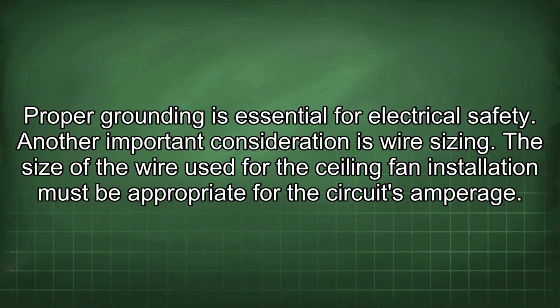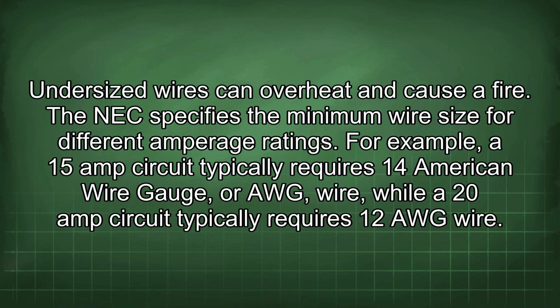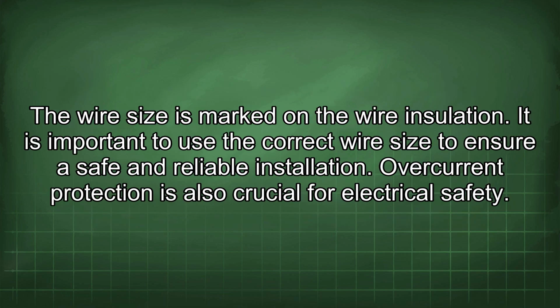Another important consideration is wire sizing. The size of the wire used for the ceiling fan installation must be appropriate for the circuit's amperage. Undersized wires can overheat and cause a fire. The NEC specifies the minimum wire size for different amperage ratings. For example, a 15 amp circuit typically requires 14 American wire gauge, or AWG, wire, while a 20 amp circuit typically requires 12 AWG wire. The wire size is marked on the wire insulation. It is important to use the correct wire size to ensure a safe and reliable installation.